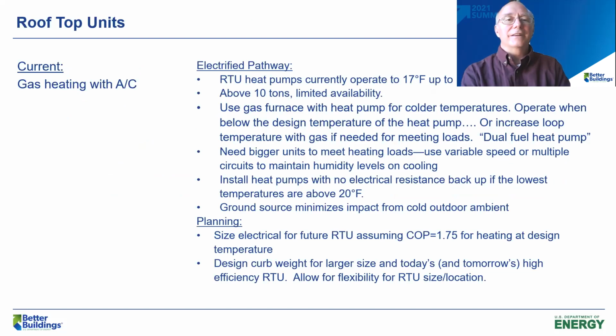So what I've done is I've kind of segregated these into some different topic areas and said, okay, if you've got a rooftop unit and here's where you are currently, what might be an electrified solution to that? And if you're not quite ready for that, what things can you do to kind of plan for that? As I started the discussion, these temperatures and sizes are things that I have found, things that I've seen installed. The availability of some of these is limited. So in this case, rooftop units up to 10 tons seem to be fairly readily available. After 10 tons for heat pumps, you'll find them in a lot of cut sheets, but they may have more limited availability. You do have to ask, and you do have to do some homework around some of this.